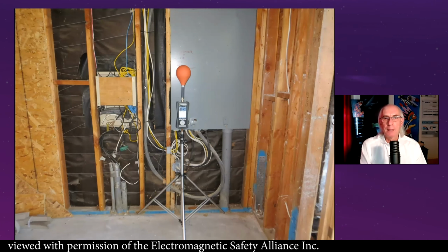So upon coming out there and doing some measurements, we recommended to the client not to use that as a headboard wall and use the opposite wall. However, the client said, try your best and try to eliminate the fields.